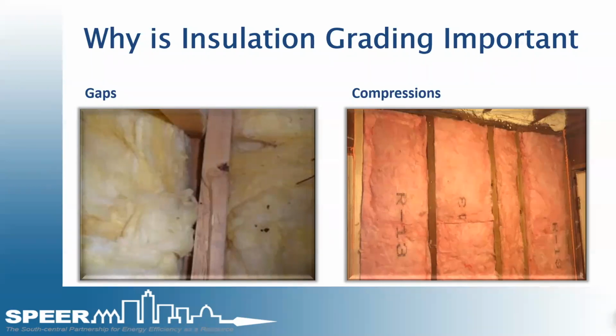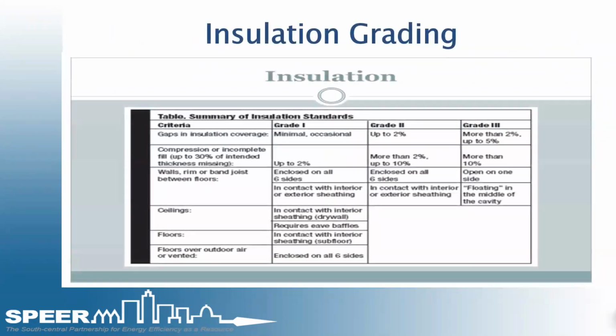Having compressions is almost as bad because you're still moving that condensation point inside the interior of the wall, and then bad things can happen due to that. Getting called back from a builder or a homeowner and asking them to run a blower door and a duct blaster because they're having either humidity issues or condensation issues inside the home, or even unfortunately mold inside of it, you come up with inconclusive findings. It's not usually due to air leakage. It's more likely due to voids or gaps in the compression that's allowing for the condensation point to move into the house itself, or at least up to the sheetrock wall, allowing for that condensation to happen.